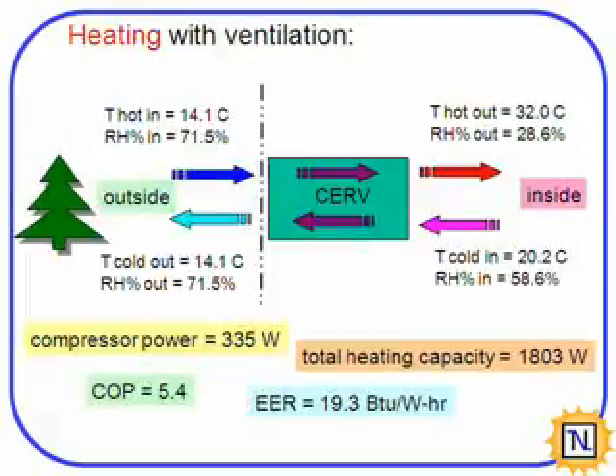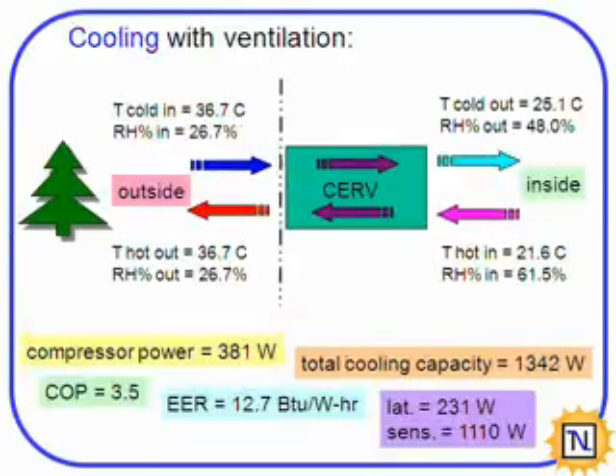This is heating with ventilation, so this is allowing fresh air to come into the unit. We're going to take inside air and remove some of the heat from that. So this is where the energy recovery is being done. Outside air is coming in, we're adding that heat, it's coming in at 32 degrees, and then we're expelling this inside air cooler. So we have 330 watts, and our total heating capacity is 1803. So here we have quite a large coefficient of performance, and the energy efficiency is good as well. And then cooling with ventilation is the same way.